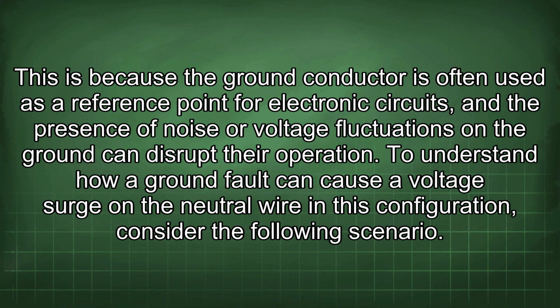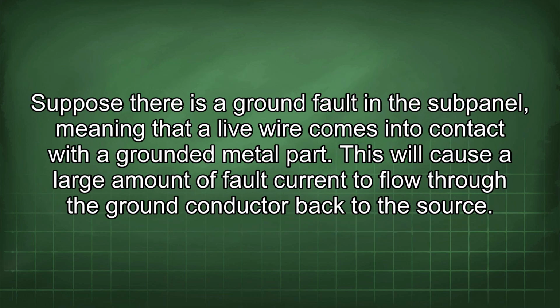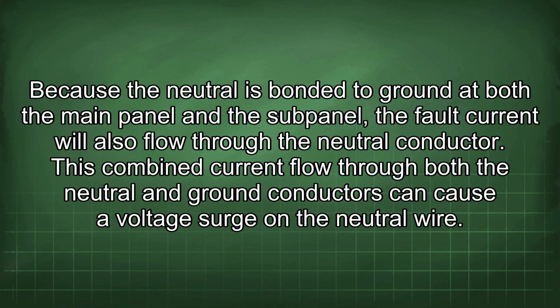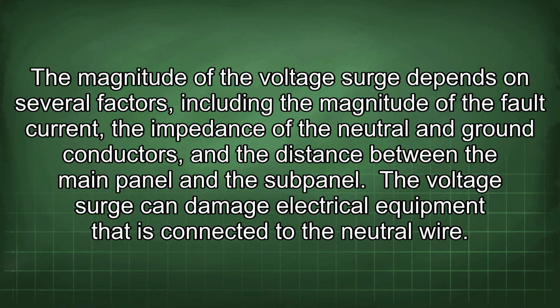To understand how a ground fault can cause a voltage surge on the neutral wire in this configuration, consider the following scenario. Suppose there is a ground fault in a subpanel, meaning that a live wire comes into contact with a grounded metal part. This will cause a large amount of fault current to flow through the ground conductor back to the source. Because the neutral is bonded to ground at both the main panel and the subpanel, the fault current will also flow through the neutral conductor. This combined current flow through both the neutral and ground conductors can cause a voltage surge on the neutral wire. The magnitude of the voltage surge depends on several factors, including the magnitude of the fault current, the impedance of the neutral and ground conductors, and the distance between the main panel and the subpanel.